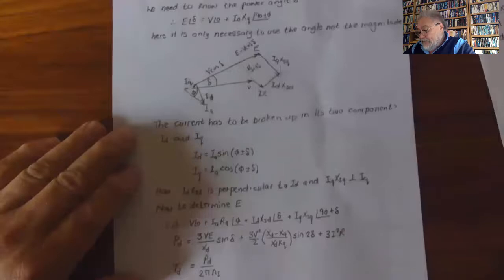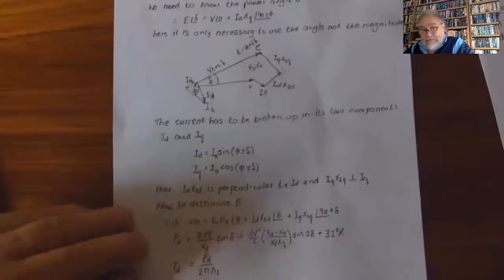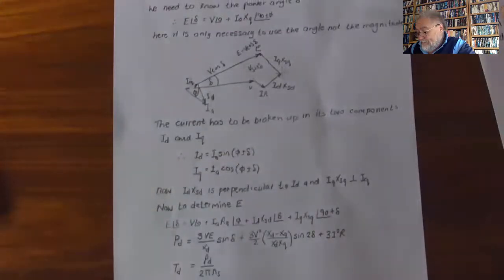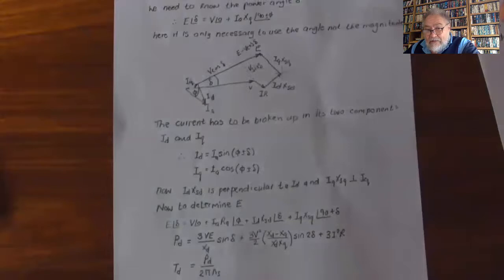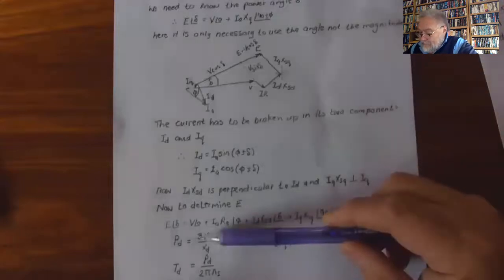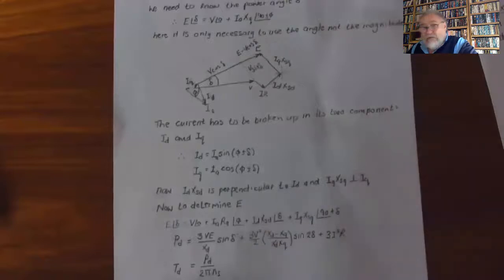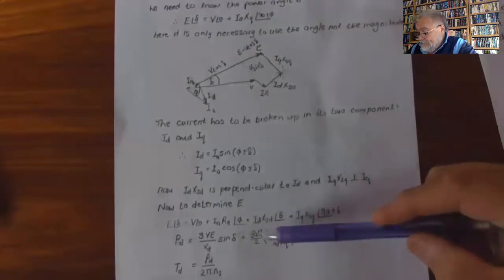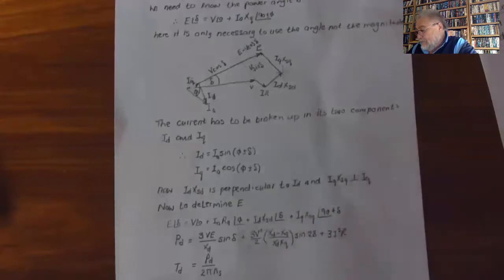The developed power is: P = 3VE/Xd · sin(δ) + 3V²/2 · (Xd − Xq)/(Xd·Xq) · sin(2δ) + 3I²R. The developed torque equals developed power divided by 2π·ns. The first part is called the power due to excitation and the second part is called the reluctance power.